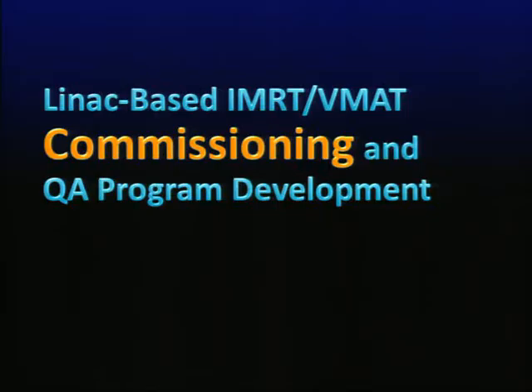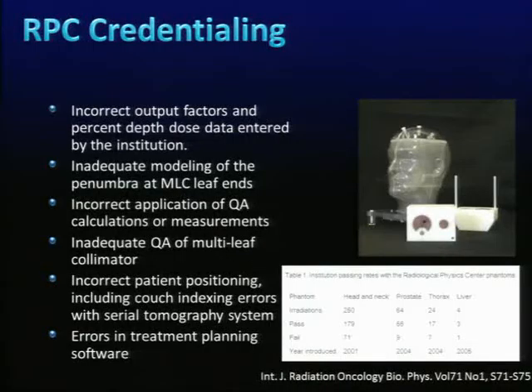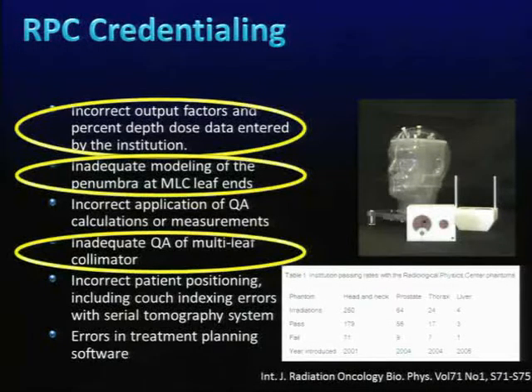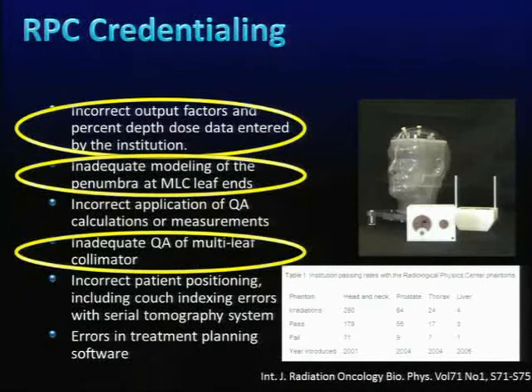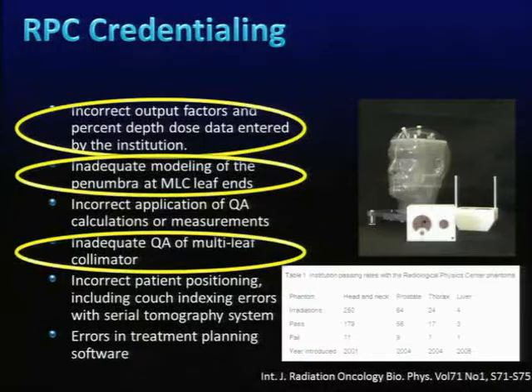My name is Grace Kim and I'm focused on the commissioning part of VMAT. According to RPC credentialing data, the main reasons for commissioning failures include incorrect output factors, inadequate modeling of the penumbra and MLC, and inadequate QA of MLC leaf calibration. This highlights how important a proper commissioning procedure is.